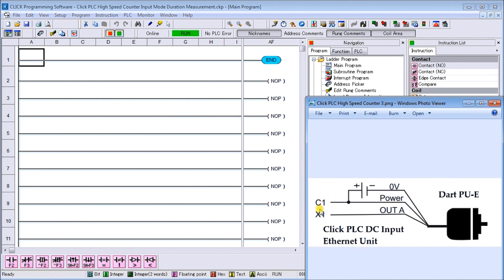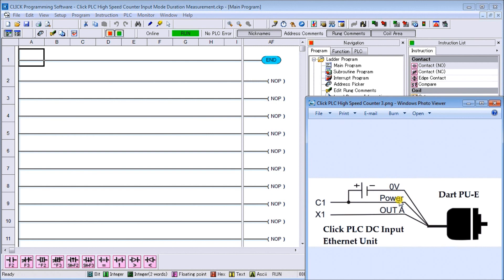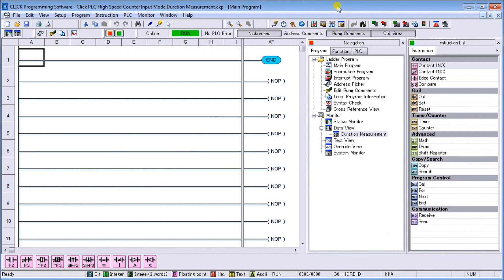Our input X1 will be connected to our signal switching on the dart, which is the white wire. Our power wire, which is our red wire on the dart, is going to the plus 24 volt. The black wire on the dart will go to 0 volt DC. That is our wiring diagram.